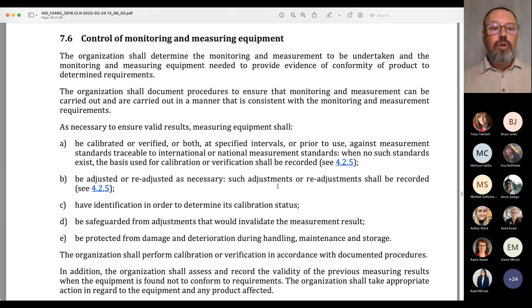So A, very simply, it has to be calibrated or verified. And there's a little bit of a difference between those two. So a calibration is obviously a one-time event where you evaluate a particular piece of equipment against a standard. A verification might be something, I see this frequently for things like scales. Okay, so maybe you have a scale that you use to weigh components, and rather than calibrate it, you have a 50-gram weight, and every day at the beginning and the end of the shift, you take that 50-gram weight, you put it on the scale, and you verify that the scale is still operating in the range that it's supposed to be operating in. So you can do it either way.